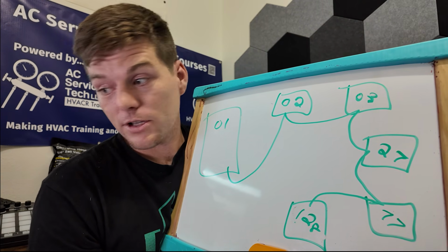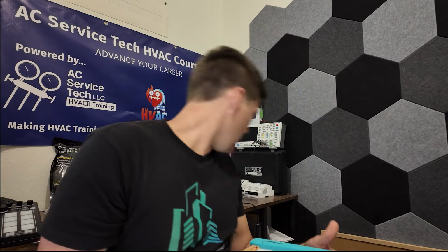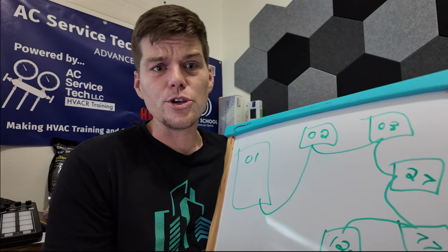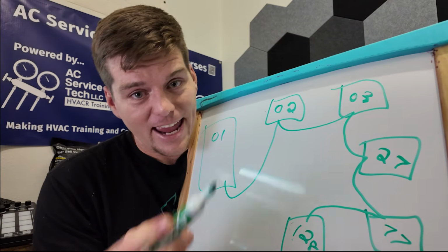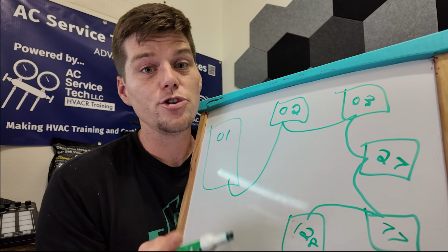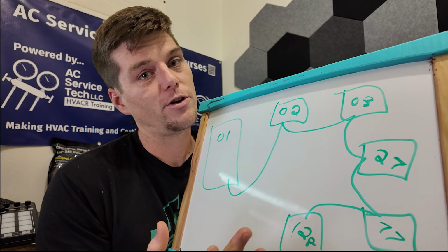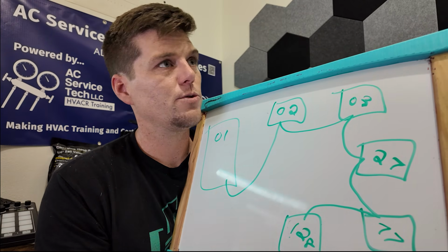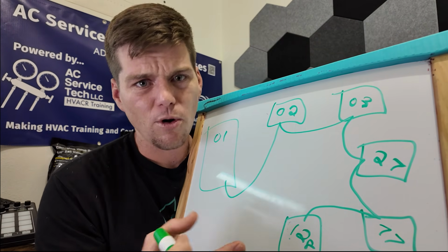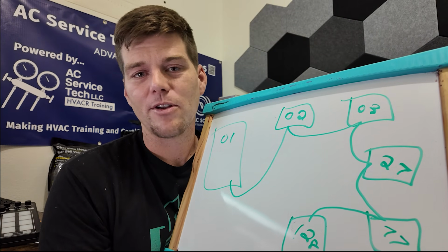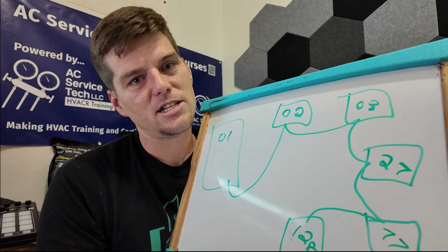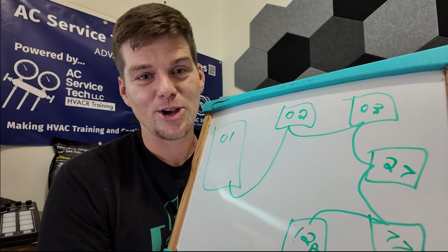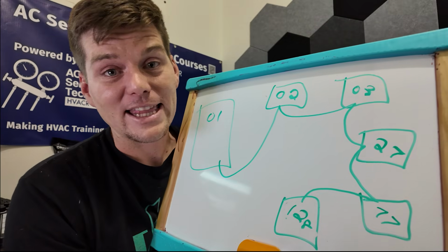When I say measuring output voltage, the A1P board, which I'm sure I have one here somewhere in my office, I've got probably 17 of them at all times, it tells you that the F1, F2, in and out on that A1P board should be 16.5 volts DC. Now that's in a perfect world with nothing connected. Really, when you see loaded communication with 28 indoor units or 32 indoor units, you're getting voltage closer to 15.4, 15.2 volts DC, depending upon the age of the system. You're never going to see that 16.5 perfect voltage. If you see that perfect voltage, it sees nobody on the network. And that is also another red flag in communication problems like this.